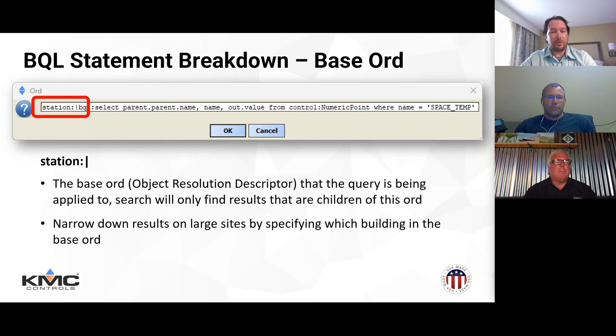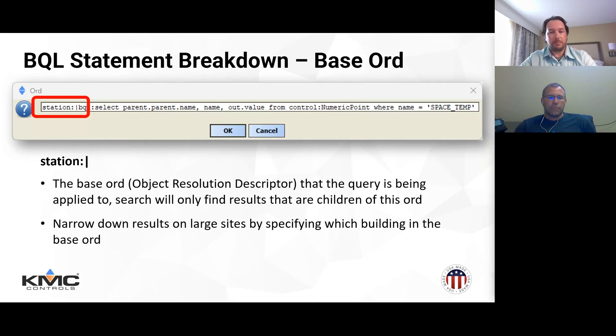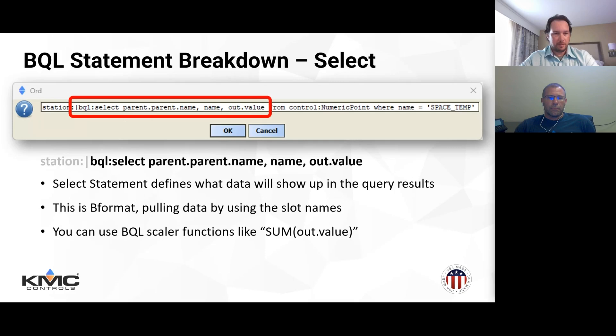The first part of the statement is the base ORD that the query is applied to - your search results will only be components that are children of that base ORD. An ORD is an Object Resolution Descriptor - basically the Niagara URL for objects inside the station. If you've got a large university or multiple buildings, you can really define down where you want to search in that base ORD. The next part is the SELECT portion, where you define what data you'll get - in this example, parent name, name, and out value, which will be the columns in the results table.